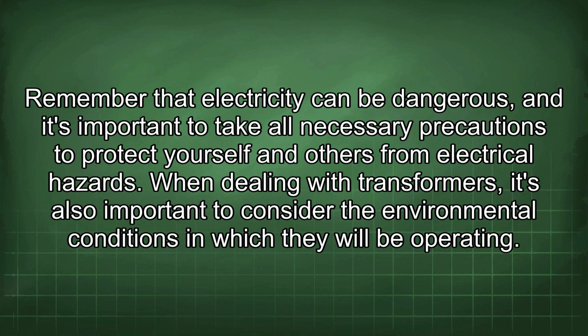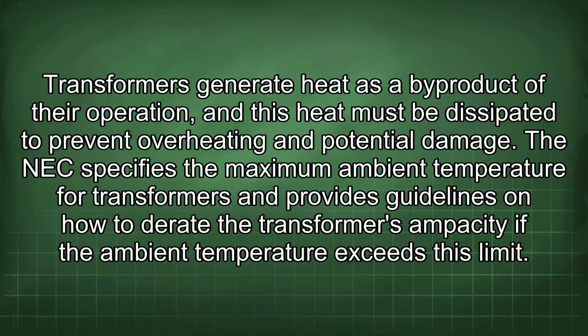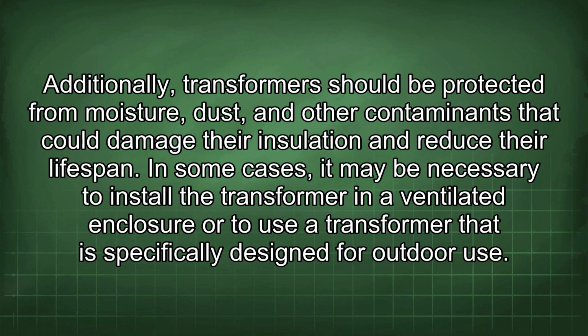When dealing with transformers, it's also important to consider the environmental conditions in which they will be operating. Transformers generate heat as a byproduct of their operation, and this heat must be dissipated to prevent overheating and potential damage. The NEC specifies the maximum ambient temperature for transformers and provides guidelines on how to derate the transformer's ampacity if the ambient temperature exceeds this limit. Additionally, transformers should be protected from moisture, dust, and other contaminants that could damage their insulation and reduce their lifespan. In some cases, it may be necessary to install the transformer in a ventilated enclosure or to use a transformer that is specifically designed for outdoor use.